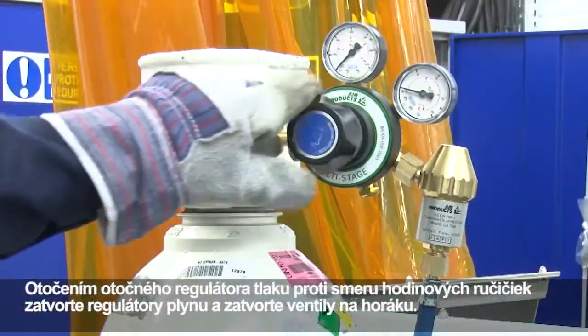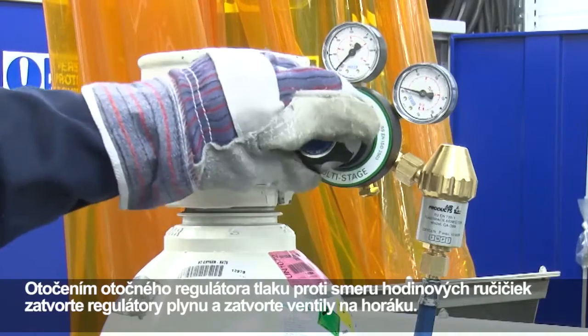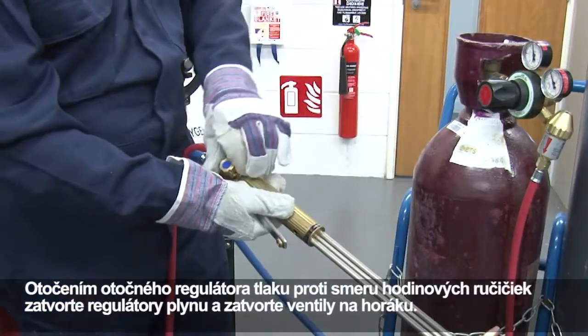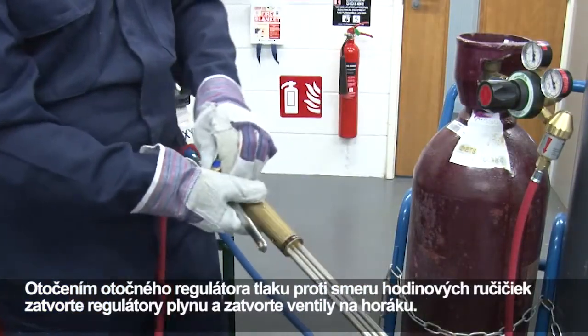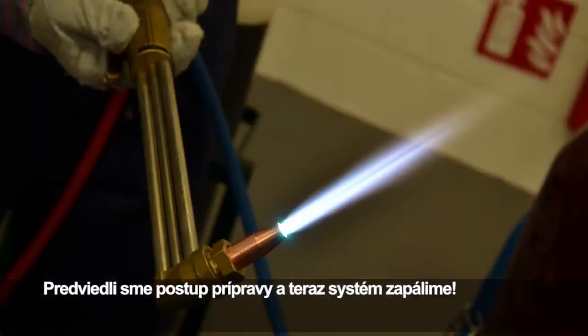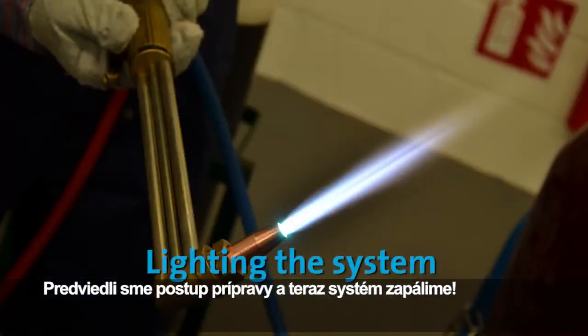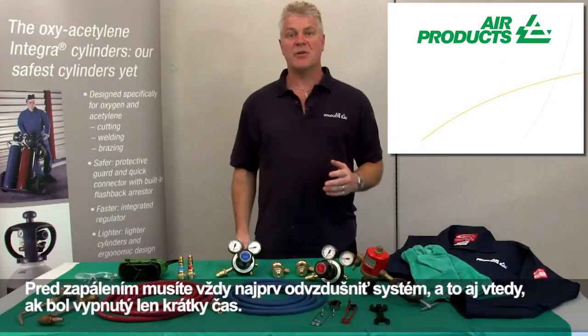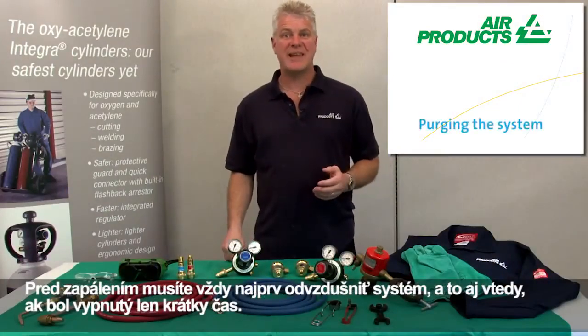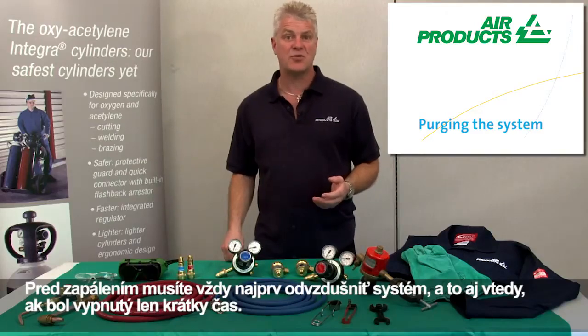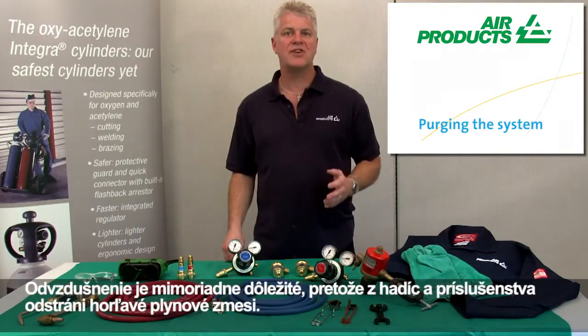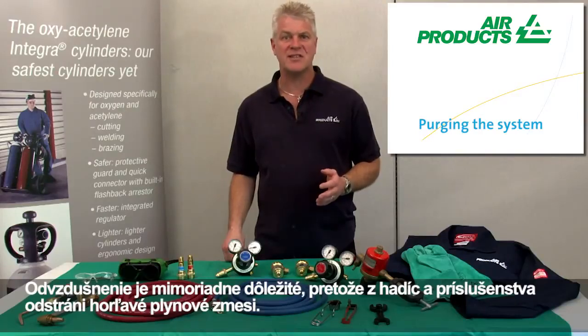Close down the gas regulators by turning the pressure adjusting knob in an anti-clockwise direction and close the valves on the torch. We've shown the setting up procedure. Now we're going to light the system. Whenever you light up, you must first purge the system, even if it's only been turned off for a short period. Purging is extremely important as it removes flammable gas mixtures from the hoses and equipment.